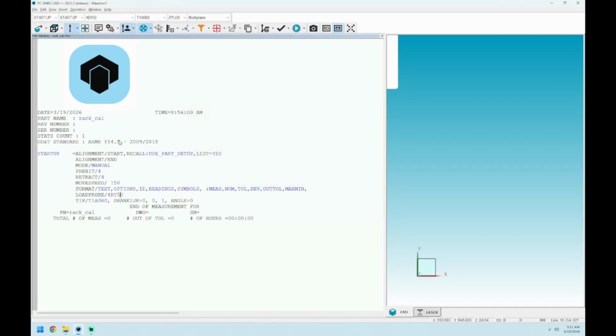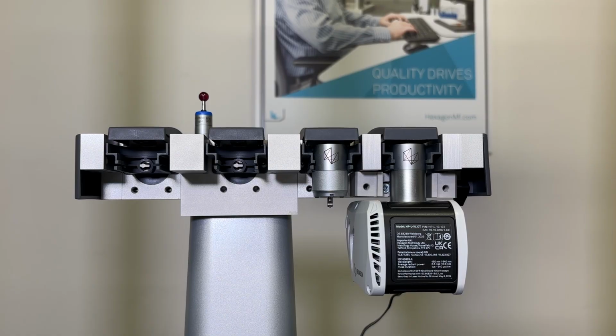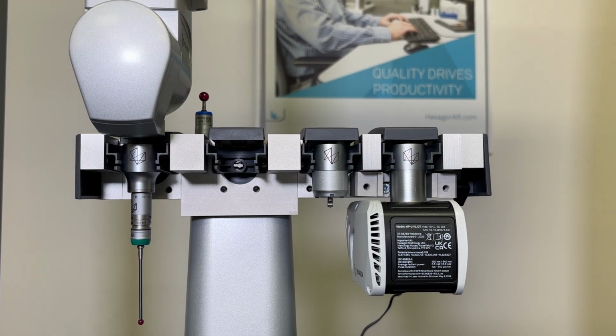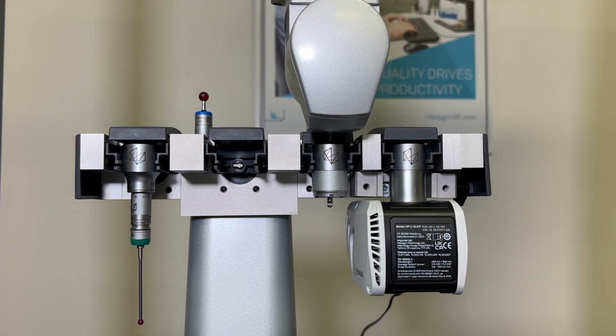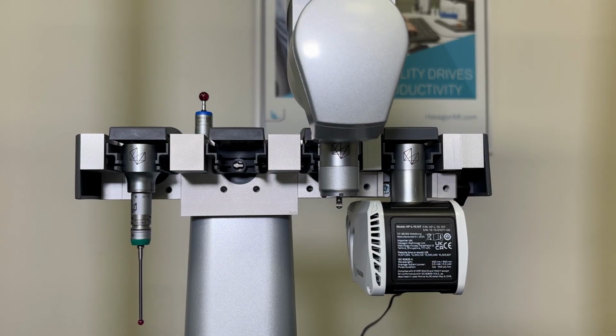The third port is going to be the laser extension, and the fourth port will have the laser. In addition to the laser, I need to have the laser extension specified in that port as well, so that PC-DMIS knows that it is allowed to pick up the laser with that extension. Once I'm done with that, I'll hit apply. And now that I'm fully calibrated and set up the rack, I'm free to do a probe change. Here I am switching from the 4x50 touch trigger probe to the 1010 laser.